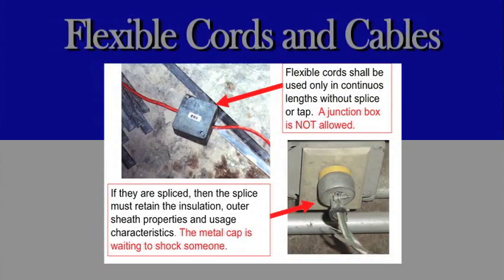Flexible cords and cables. Flexible cords shall be used only in continuous lengths without splice or tap. A junction box is not allowed. If they are spliced, then the splice must retain the insulation, outer sheath properties, and usage characteristics. The metal cap is waiting to shock someone.